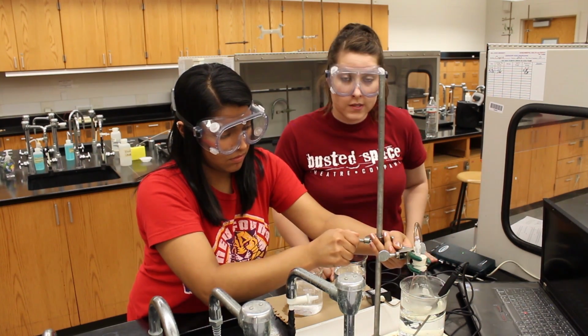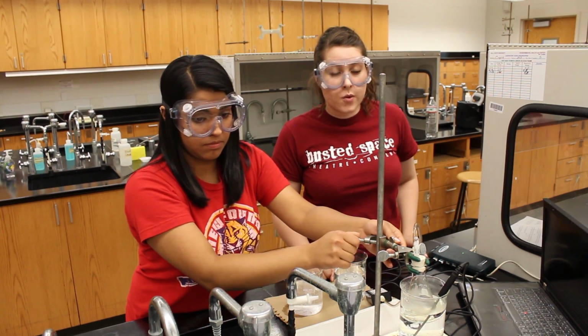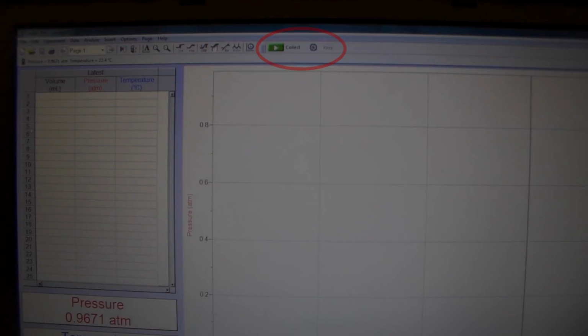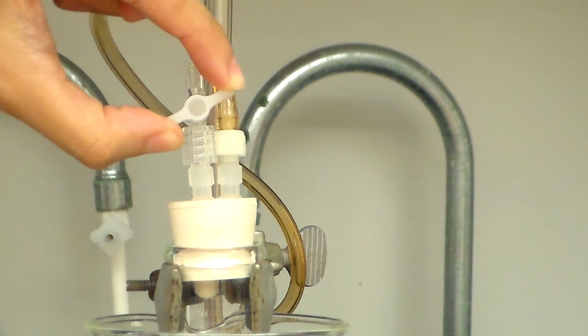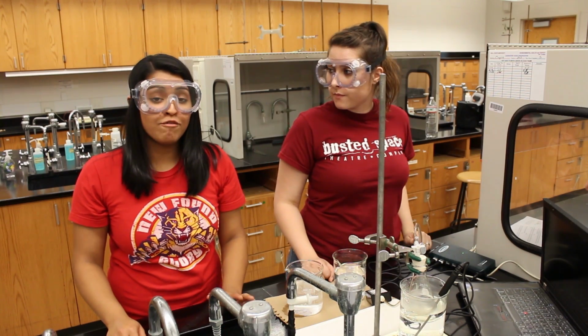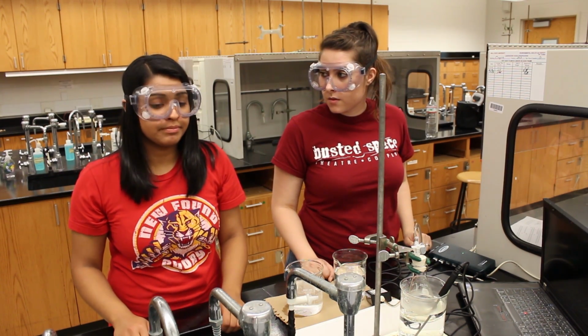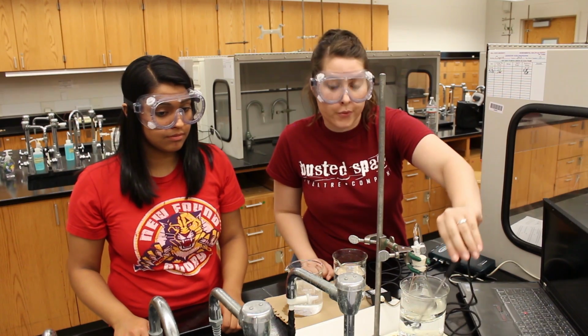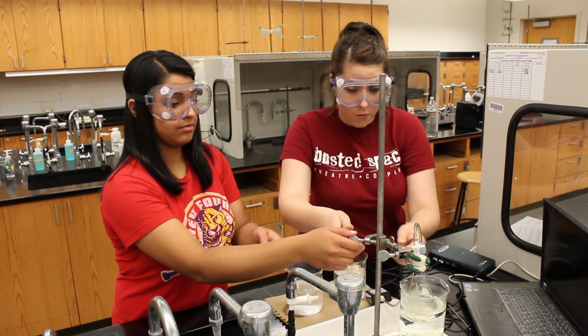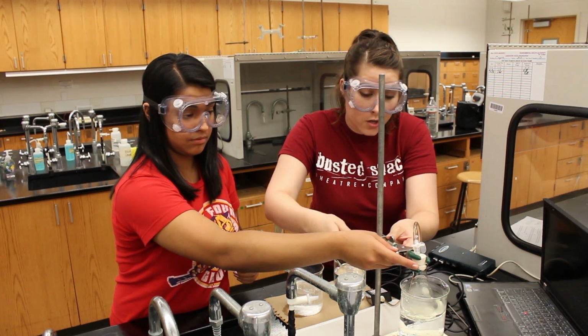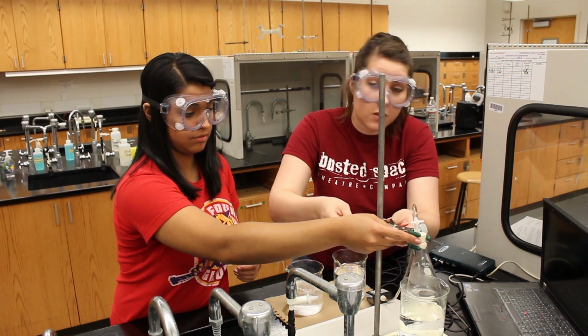Once the water boils and the temperature stabilizes, you'll want to click the collect button and close your gas valve. Wait 5 minutes and then click keep. Carefully then remove the probe and the flask from the hot water bath. Be sure to keep your valve closed.